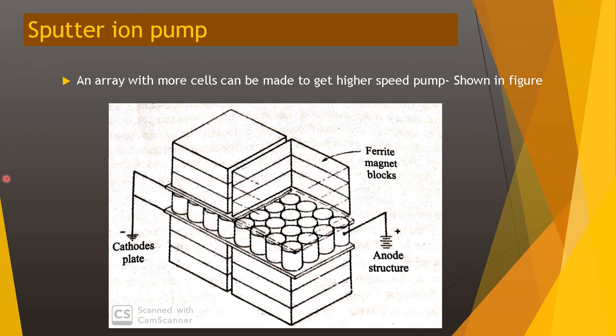An array of more cells can be used to achieve a higher speed pump. Many cathode-anode combinations are placed together. These are the anode structures, and both ends of each anode are fitted with cathode plates connected to ground. This arrangement represents a sputter ion pump array, where combining multiple cells produces a higher pumping speed.